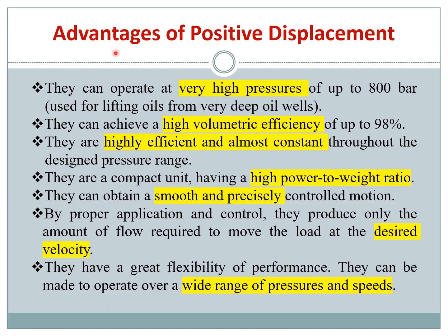All these positive displacement pumps have their own advantages. They can operate at very high pressures, up to 800 bar, compared to other types of pumps. They have a high volumetric efficiency, which can go up to 98%, meaning they are very efficient. They are highly efficient and almost constant throughout the pressure range, so they will consistently and efficiently deliver the pressure range you require.